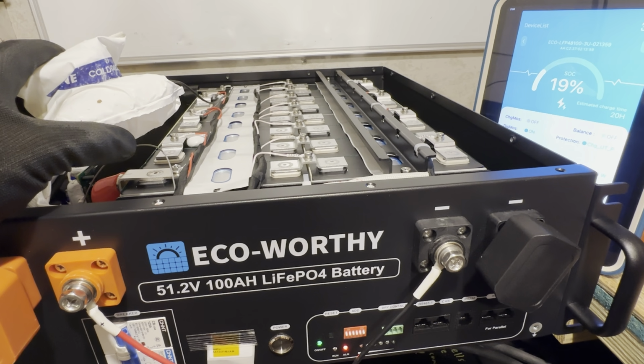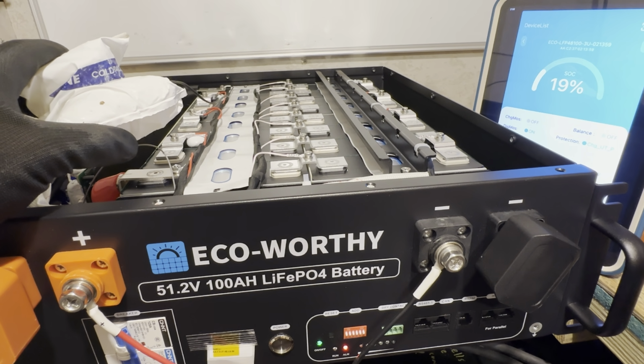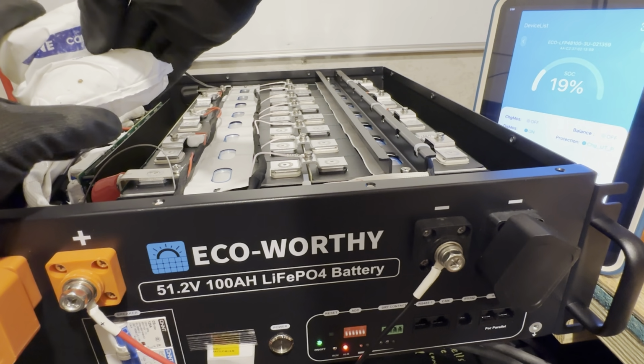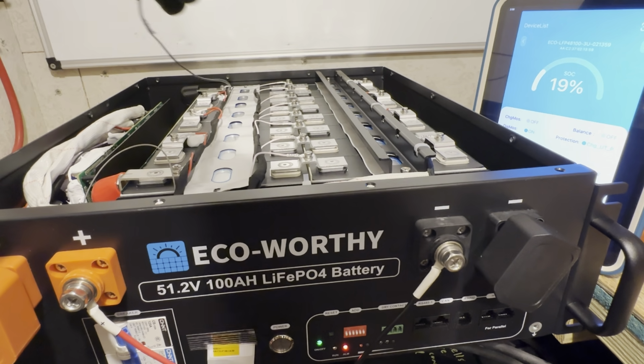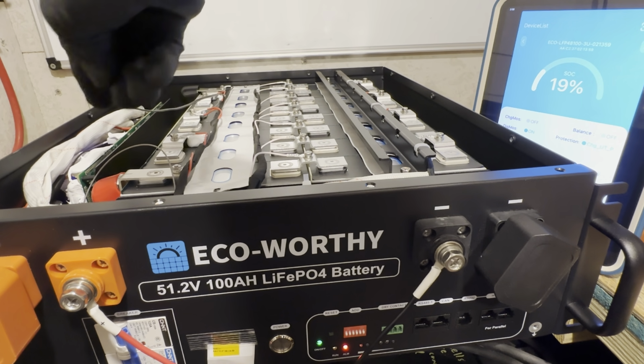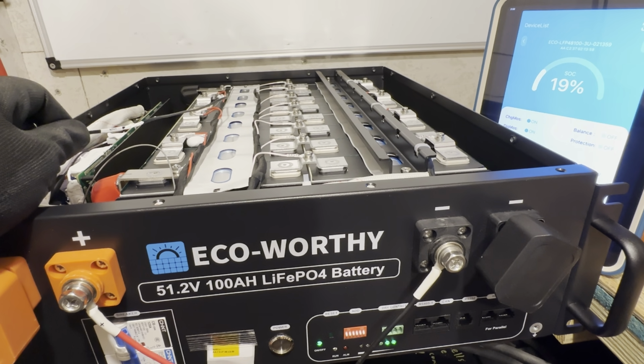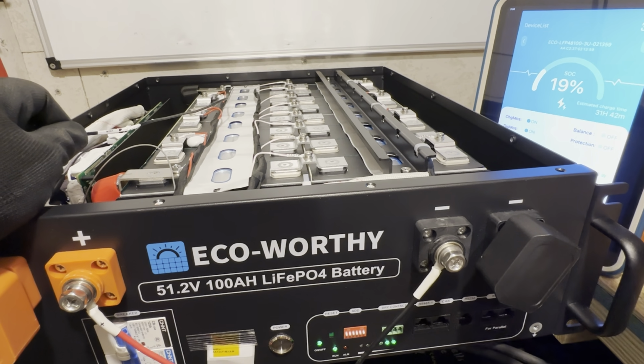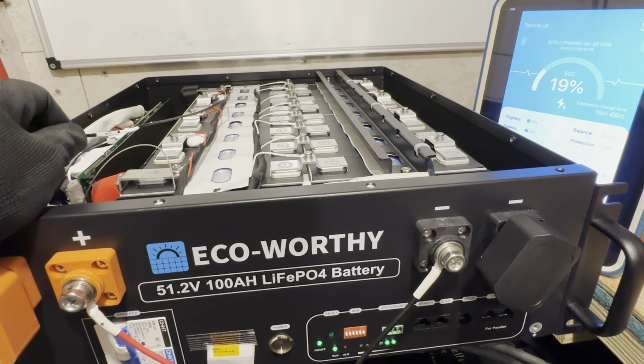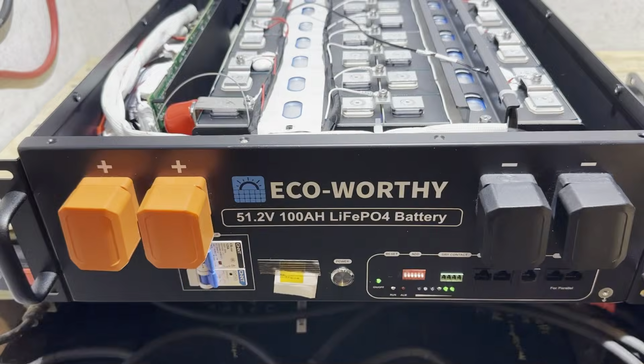All right, I heard the charger stop. There we go, charge under-temp protection. The alarm light came on right here in the front. Great, we have functioning low temp protection as expected. Let me warm the sensor back up. All right, the charger started back up, the protection display went away, and the alarm went away. Great, works as designed.